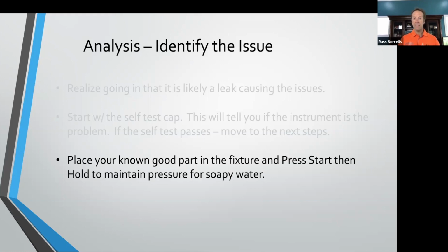So I'm going to get whatever I get out of that test, and then I'm going to press start. And then for our instruments, you can press hold, and the hold button is your friend. That's what I always tell people. The hold button is your friend, because when you can hold and maintain pressure in the part, then you can use Snoop, or in some cases soapy water, to spray onto the part, onto fittings, onto different components to identify where your leak is likely coming from. Because again, normally the problem is a leak in the circuit.